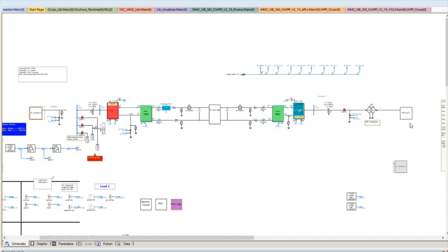However, we do the energization, or black start, from the wind power plant side. So the wind power plant is in grid-forming mode and controls the offshore voltage and frequency. Thus the offshore terminal MMC controls the DC link voltage of the HVDC link, and the onshore MMC operates in an islanded mode, which means it controls the onshore voltage and frequency, to which a block load is then connected for energization, demonstrating the energization capabilities.